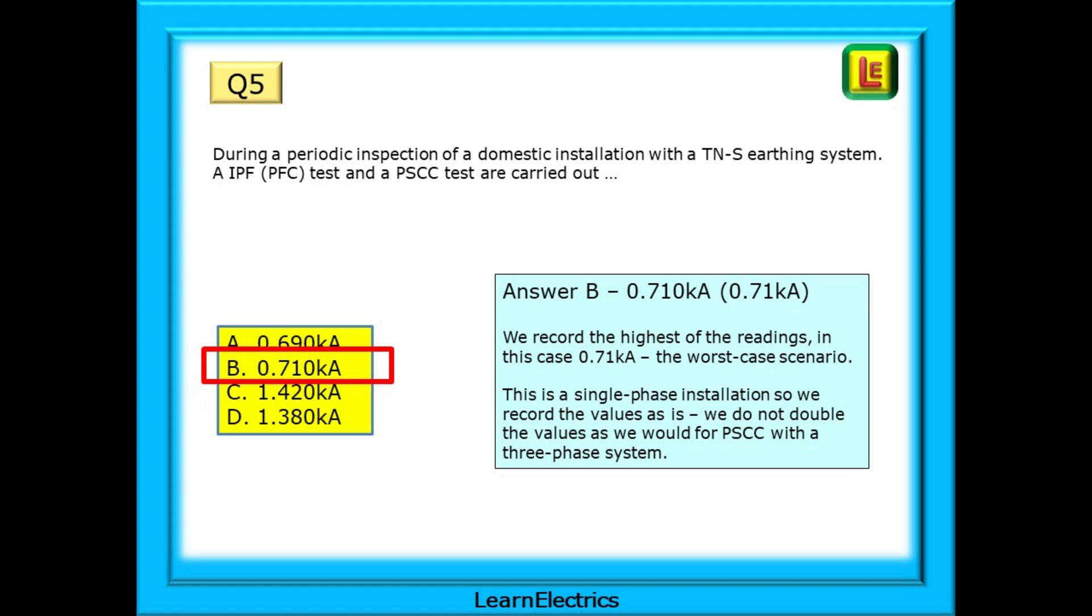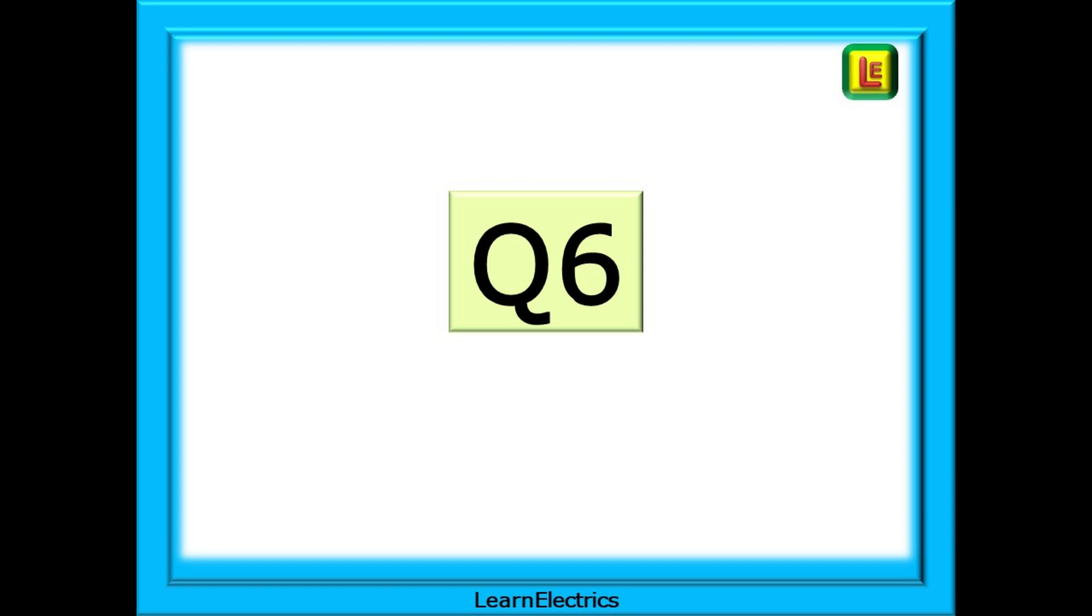This is a single phase installation, so we record the value as is. We do not double the values as we would for PSCC with a three-phase system. Question 6 is next. Be sure to read each answer carefully.